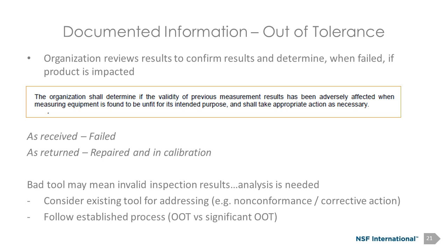The next slide talks about out of tolerance events. If we have tools and we get them calibrated or verified or both at that specified interval, we're going to have either a passing result or a failing result. If it's passed, everything is good. We've got those retained, documented information articles that demonstrate fitness for purpose. If it's failed, we want to make sure that we've analyzed the product that may potentially be at risk from the failed calibration effort.